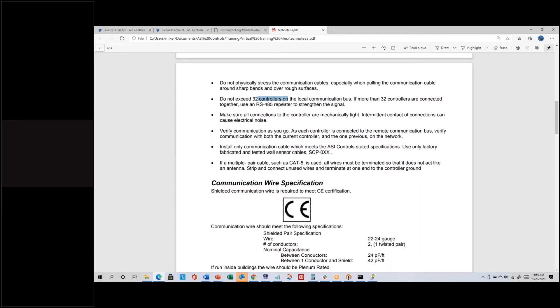The RS-485 spec says no more than 32 loads, and some controllers out there can be half or quarter load devices. In a BACnet system with 30 ASI controllers, you could add four more non-ASI half-load devices — four half loads equal two loads, so 30 ASI loads plus two non-ASI loads equals 32 total. It's not mentioned in this doc, but there's also a wiring length limitation: no more than 4,000 feet for the entire RS-485 daisy chain.